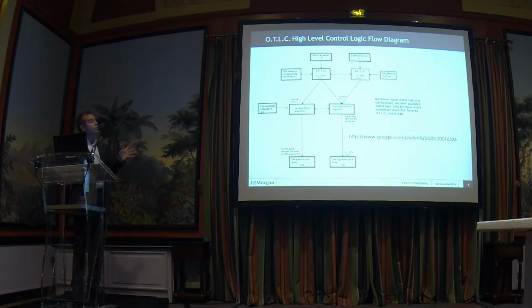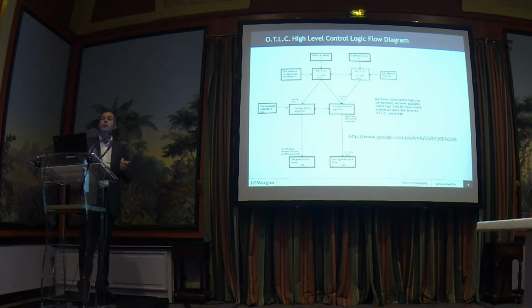By having this system, it's basically leveled out all the machines running, with the N+25 resiliency we've got. Now I can leverage all the machines and make them all run on an even keel. But the moment something goes wrong, be it supply water temperature or return, or someone goes around and starts shutting vents or blocks something, the system will detect it and start to ramp up. So in essence, it's a way of controlling all your machines without interconnection between the machines. They don't talk to each other, they just work purely on return air temperature.